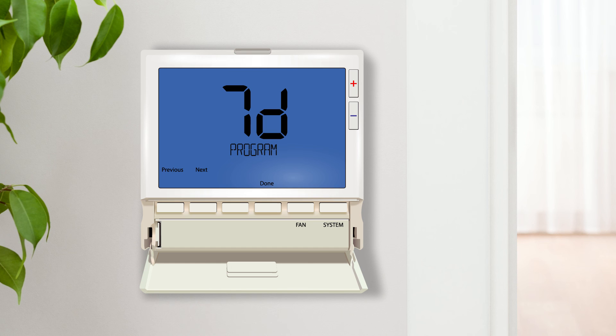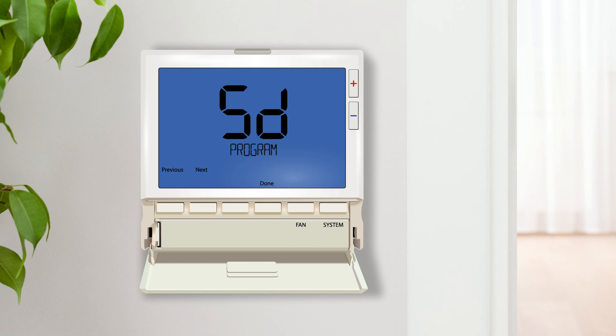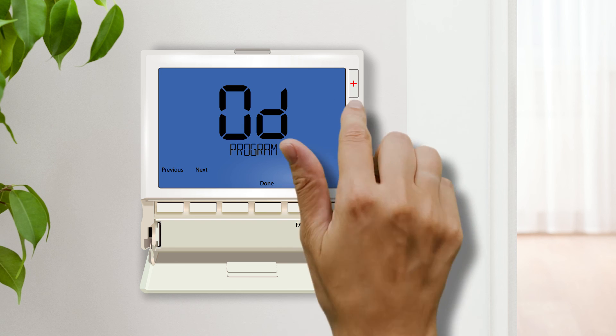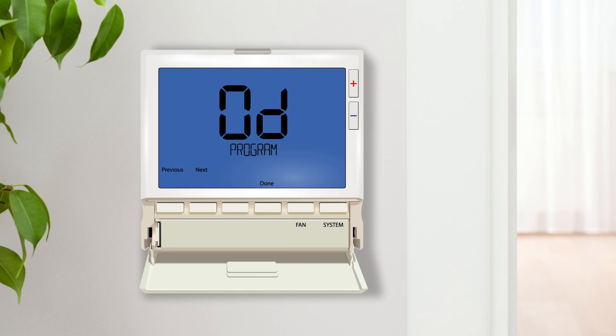Multiple programming options are available depending on the needs of the homeowner. Selecting 7-day will allow you to customize each day of the week individually. 5-1-1 groups the weekdays together to save time and 0-day turns scheduling off altogether. 7-day or 5-1-1 is required for any tech setting that utilizes time periods, such as economizer mode.